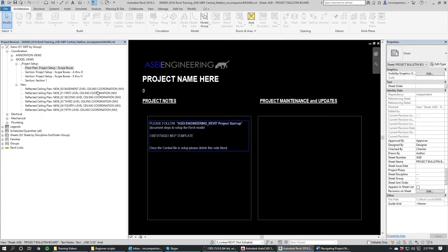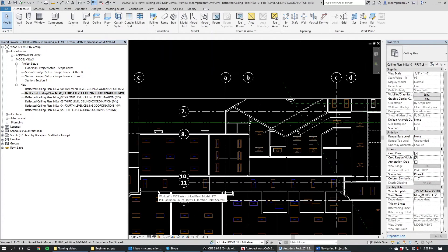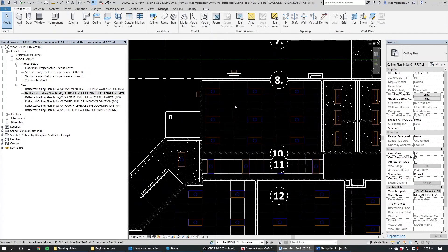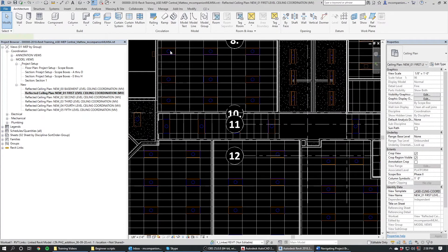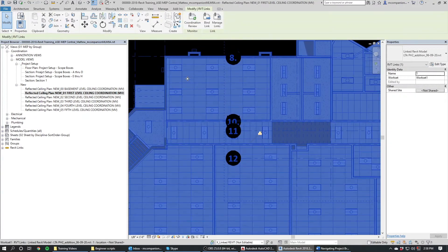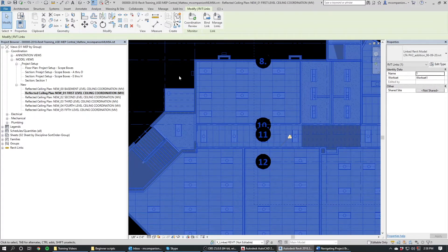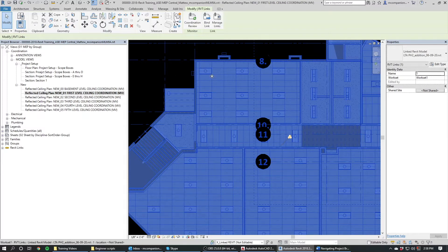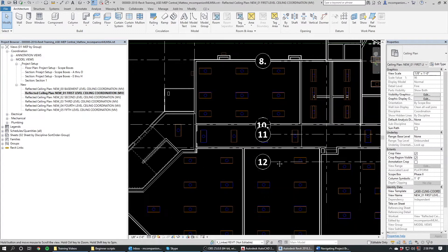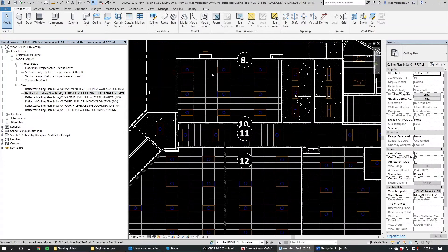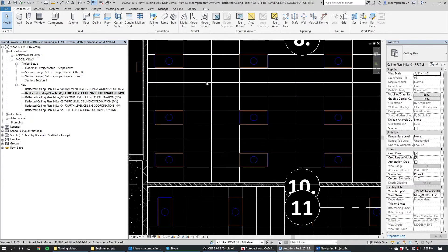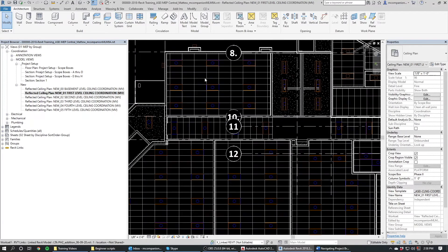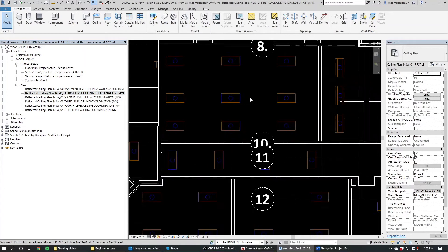Coming up next would be our ceiling plans. These ceiling coordination views are mostly here for mechanical. This is where mechanical needs to come to place their diffusers. This is where your ceiling is going to be shown. As electrical places their lights, these are architectural lights, so they're probably not even in the right place anyway. Electrical does tend to place as close as they can to architectural locations, but this one looks a little wonky here. So they're probably going to go down this row instead of that row. But even still, as electrical places their lights, they will populate in this view. So when mechanical comes in here, mechanical can come in, place their diffusers, line it up in the grid, and now you know that your diffusers are lined up in the grid, missing all the lights.